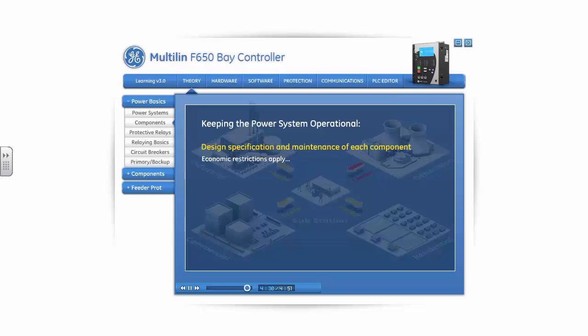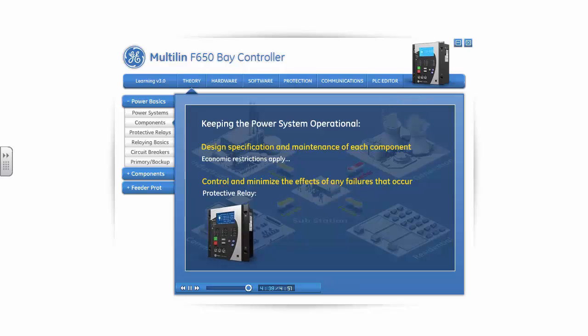The second procedure which is followed is to control and minimize the effects of any failures that do occur. This is where the protective relay fits into the power system. The protective relay is the device which operates to disconnect a faulty part of the power system, thereby protecting that part and the remainder of the system from damage.